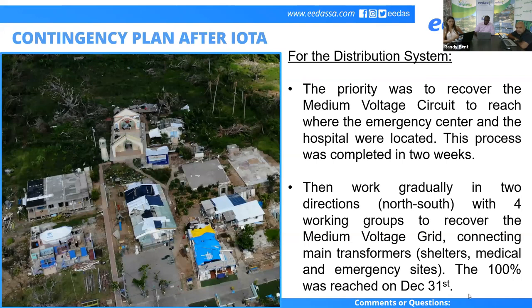Why did we deploy everything on the medium voltage grid? The basic assessment gave us the opportunity to see that the transformers and mainly the equipment could be energized. That would help people share energy, those houses that were still intact, or areas where they can connect equipment to these transformers. So we deployed every asset we had to recover the medium voltage grid. It required less personnel, less equipment was needed, and we could at least have some energy to share all around the island.